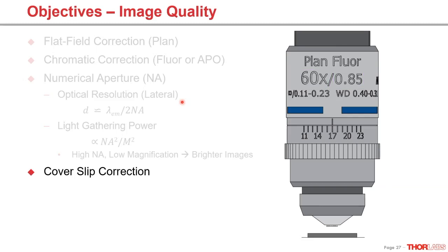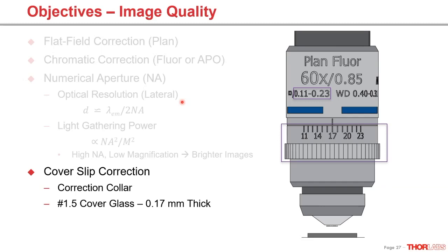A point that is often overlooked is cover slip correction on the objective lens. Some objectives clearly state the cover glass correction range — in this case 0.11 to 0.23 millimeters, and it has a correction collar for adjustment. It's important to match the correction with the actual cover slip you're using. Many objectives that don't state this on the lens are corrected for number 1.5 cover glass, which is 0.17 millimeter thickness.